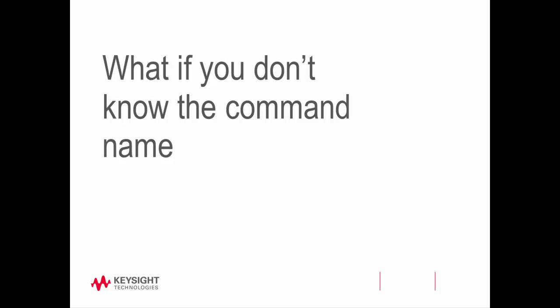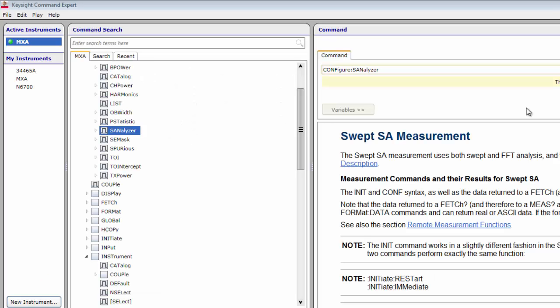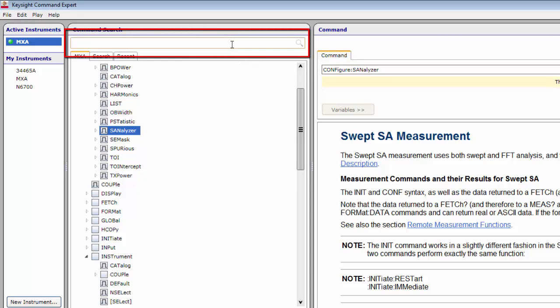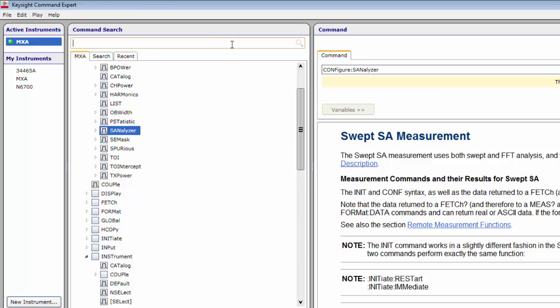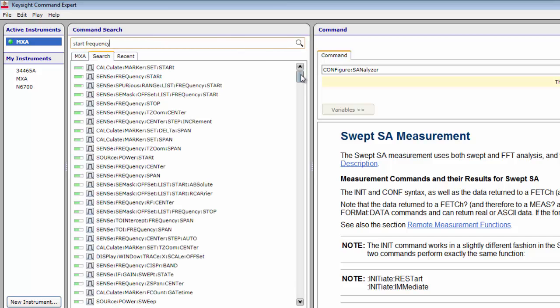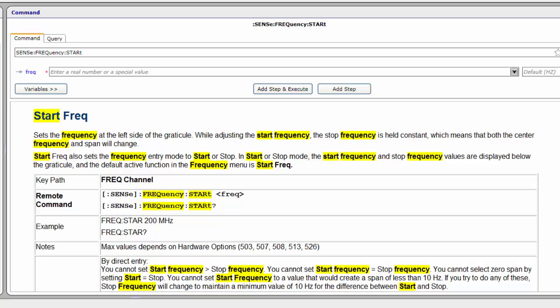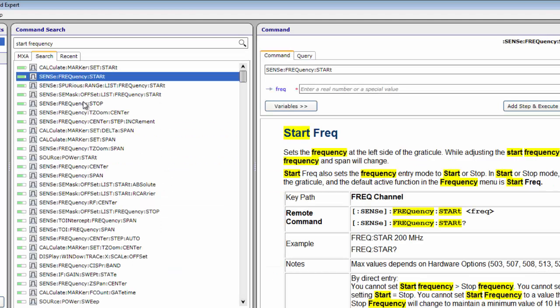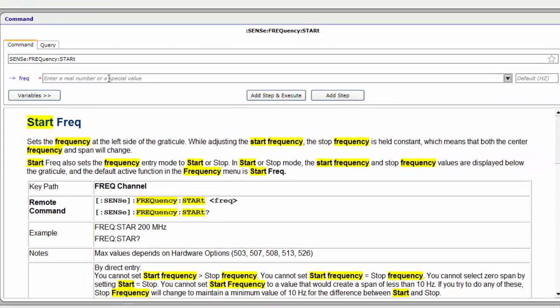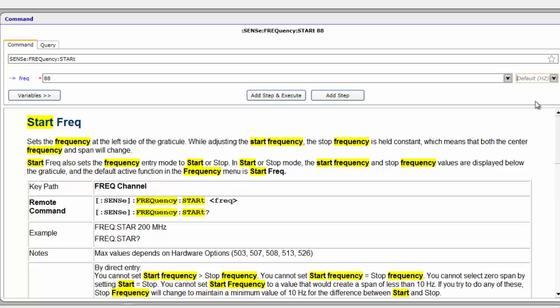But what if you don't know the command name? You can use the Command Search pane to search for SCPI commands. At the top of the Command Search pane is a field for entering command search terms. We'll search for commands to set the Start and Stop frequencies. Type Start Frequency in the search box and click the Search icon. Command Expert displays a ranked list of search results in the Search tab. To select the Start Frequency, select Sense Frequency Start. This displays the command details in the Command pane. Enter 88 as the frequency input value and select Megahertz as the units from the drop-down menu. Click the Add Step and Execute button to send the command to the instrument.